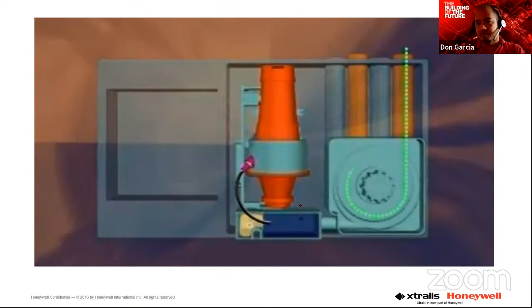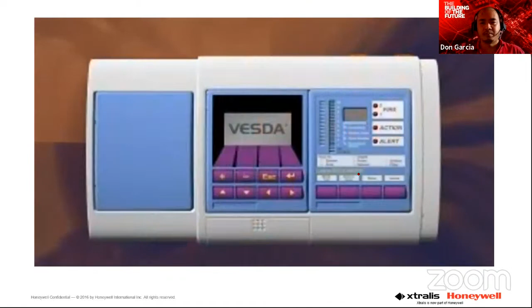During the first stage of filtration, dust and dirt are removed from the air. A portion of the sampled air goes through the second ultrafine filtration stage and introduces clean air that forms a protective barrier, keeping the optical components within the chamber free from contamination. The sample proceeds into the chamber where it is exposed to a controlled laser light source. Even extremely low levels of smoke particles present in the air sample will cause the laser light to scatter.